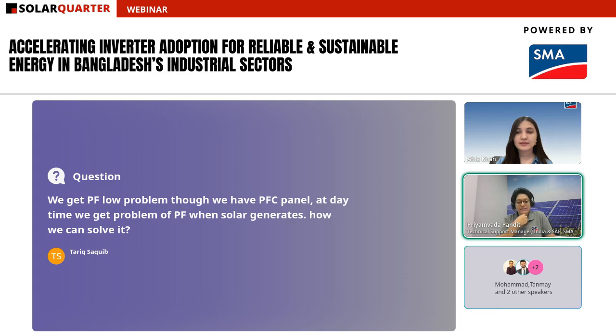But having said that, you have to always remember that whenever PV inverters supply reactive power, your active power is going to go down a bit, not in the same proportion. Solar inverters are designed and rated for apparent power. So they are rated for kVA rating, and if you are supplying reactive power, your kilowatt for the inverter is going to go down a bit.